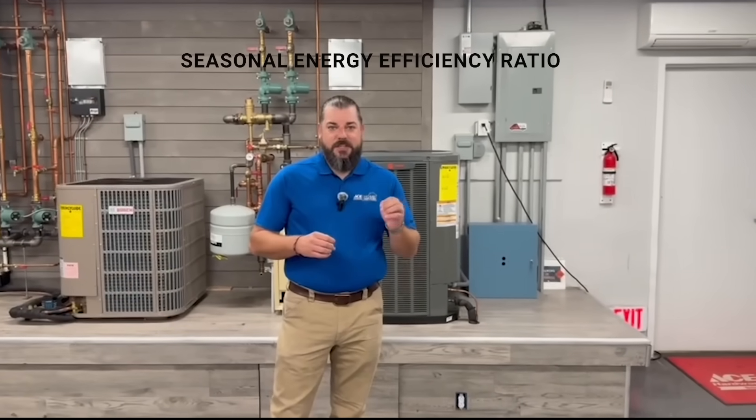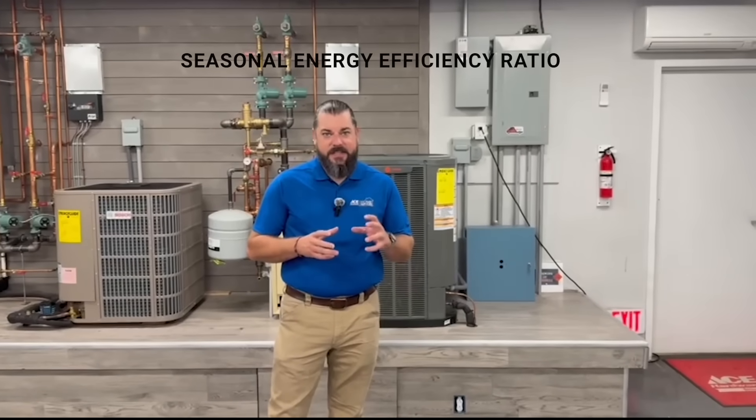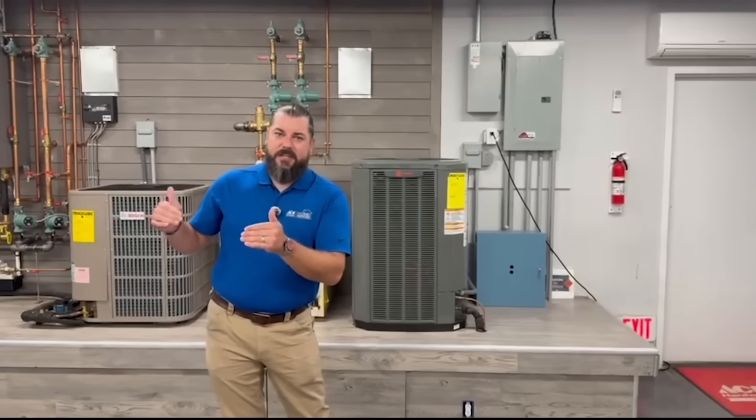That's a question we get often and it's been coming up more recently. What is SEER rating? How does it work? How do we know what to buy? What should we look for? SEER rating is your Seasonal Energy Efficiency Ratio. What that means is it's your total BTUs consumed over a given period of time — a cooling season — divided by the watts of energy that the unit uses. That gives you your SEER rating.